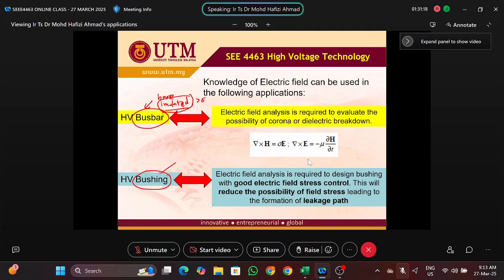Bushing is used for higher voltage or extra high voltage applications. They use condenser type bushing, which has a foil layer inside that creates capacitive grading layers. This distributes the electric field along the bushing. We are going to study this towards the end of the slides.